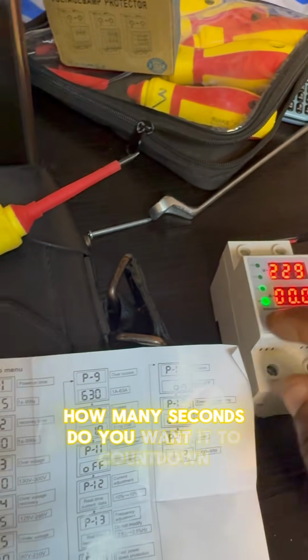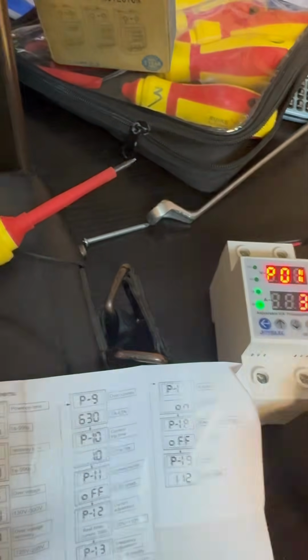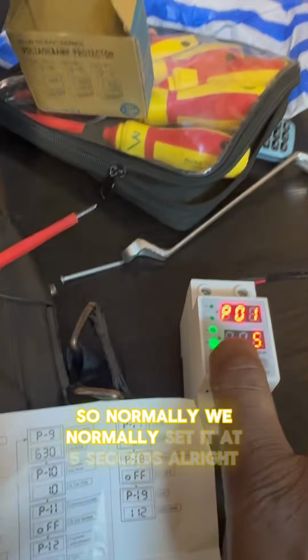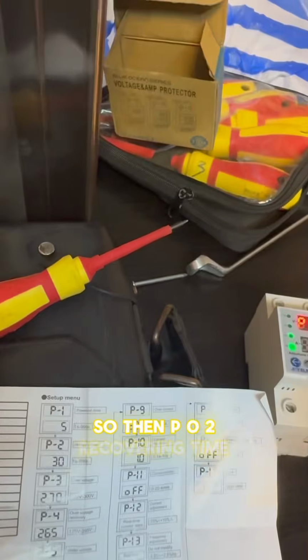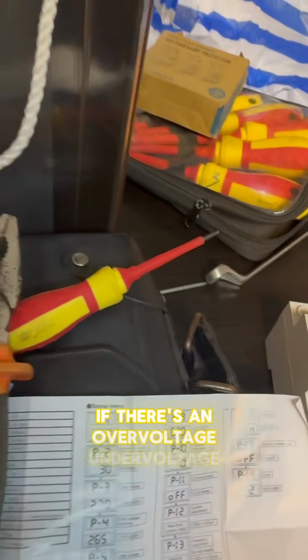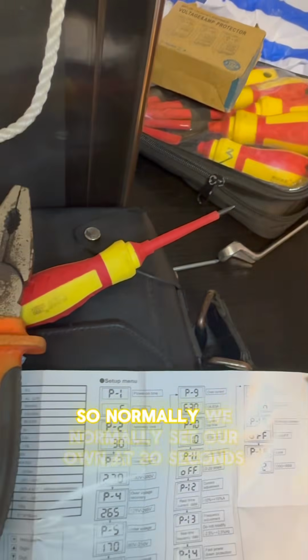By here you click on set, you will see PO1 here, which is P1. It said power on time. So by the time you plug it in, how many seconds do you want it to count down before? Normally we set it at 5 seconds. Then PO2 recovering time. If there's an over voltage or under voltage, how many seconds does it take to recover? We normally set our own at 30 seconds, so that you can have enough time to breathe.